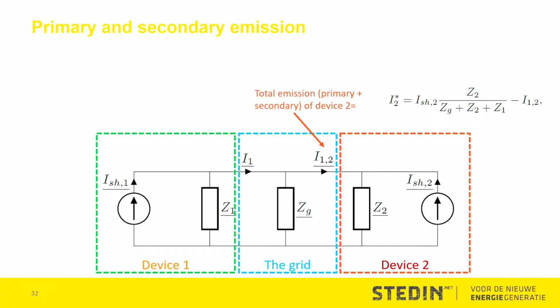This is why it is so important to test equipment on networks without additional devices, not just in the grid, but on a network you know with a clean voltage source, for instance, and do your test there. That's a way to cope with the difference between primary and secondary emission.